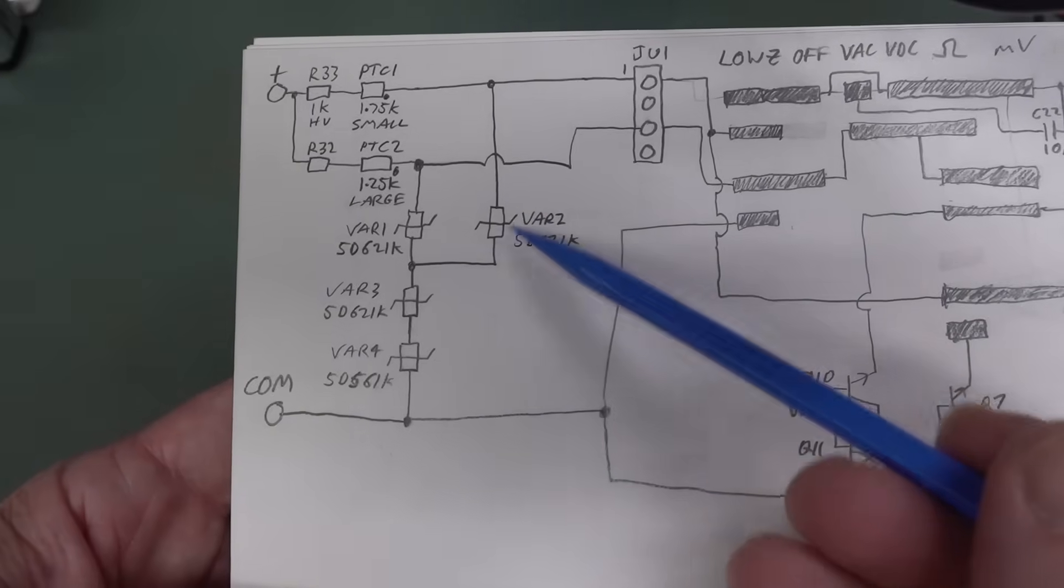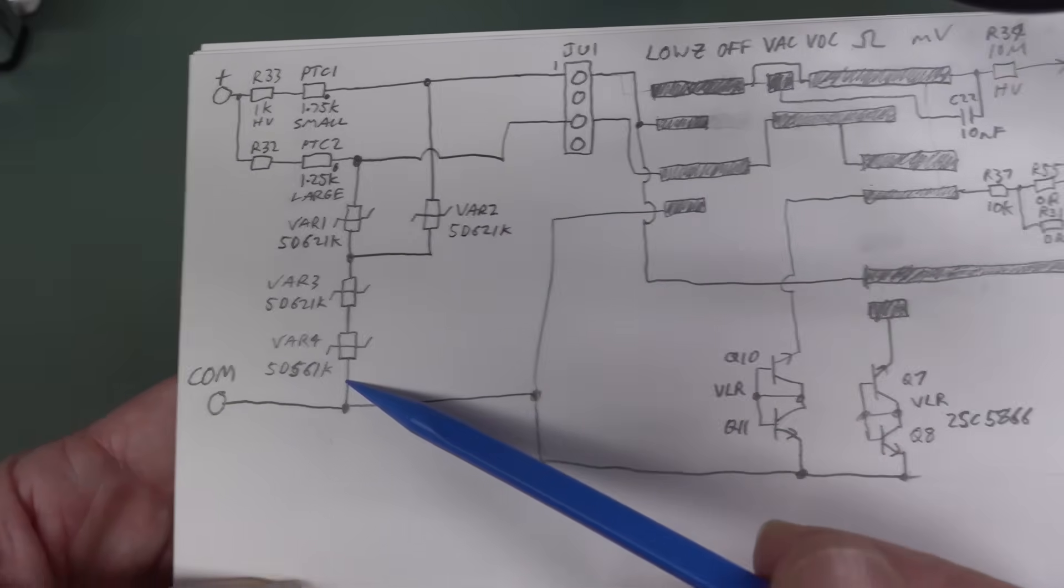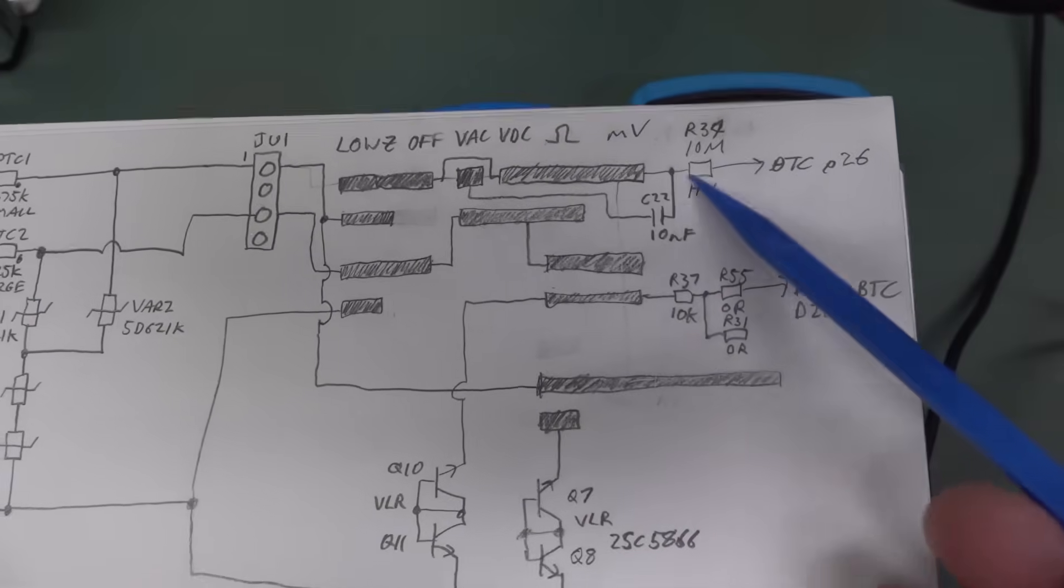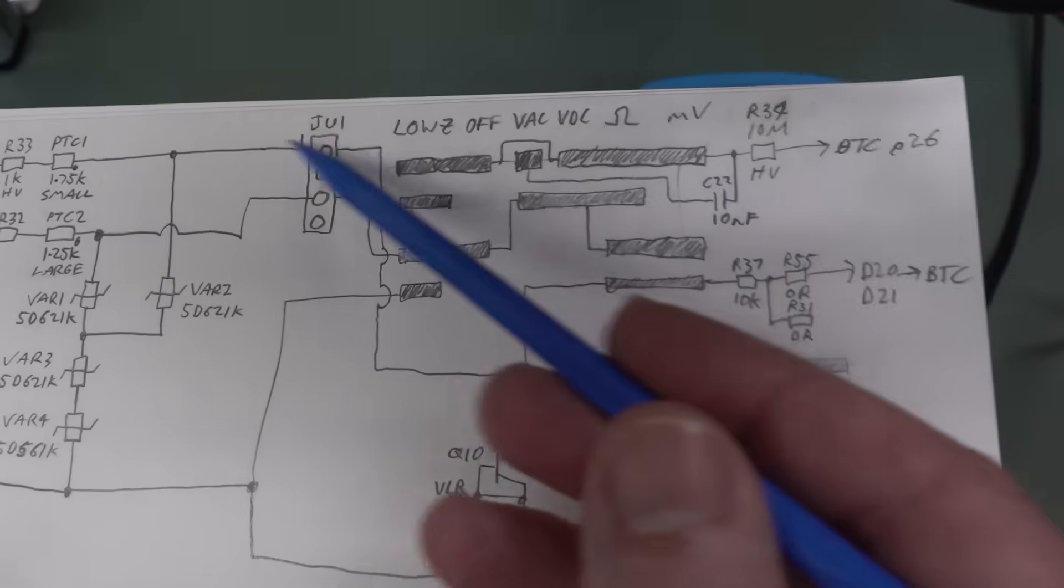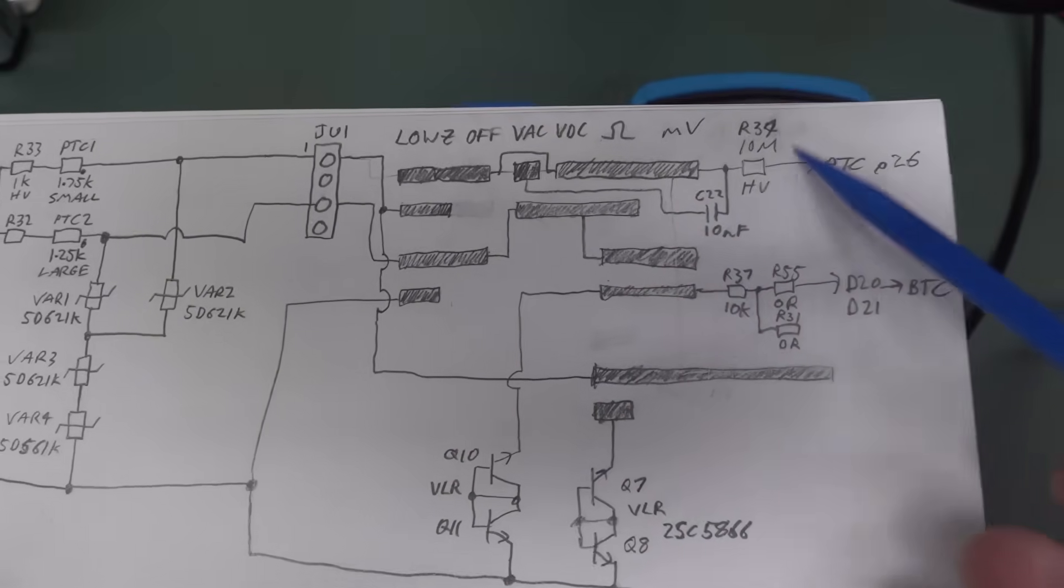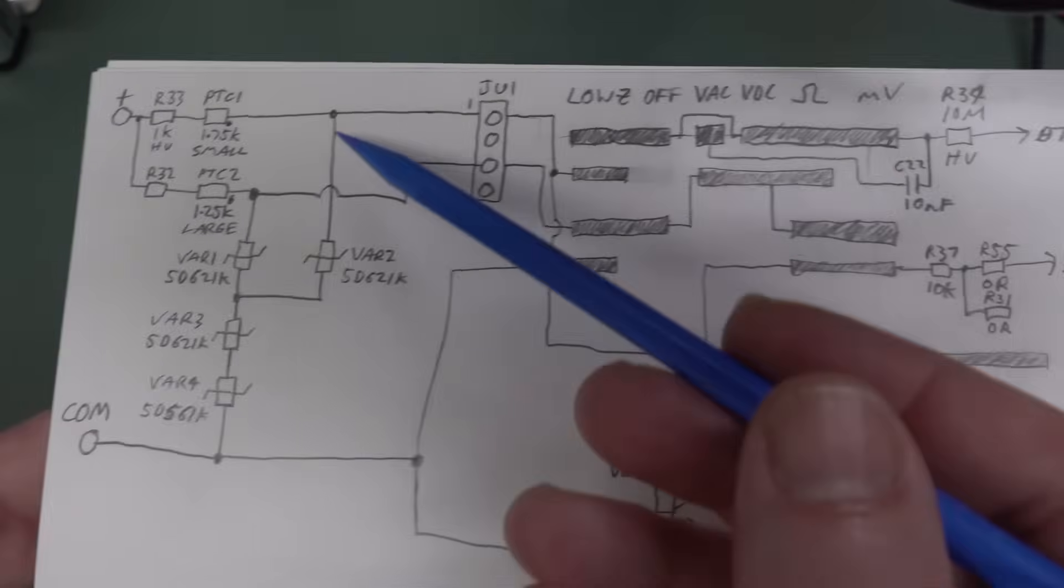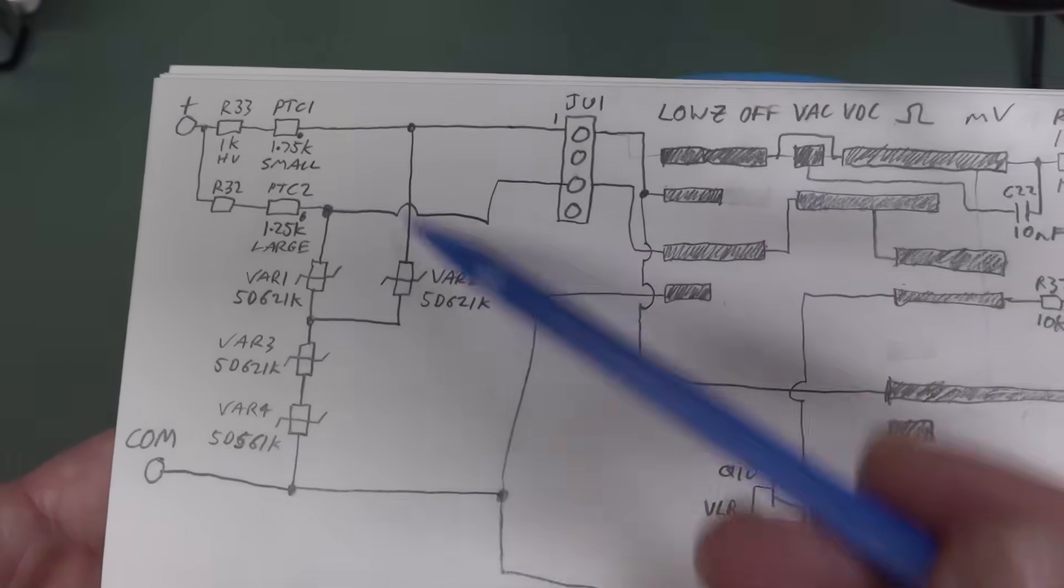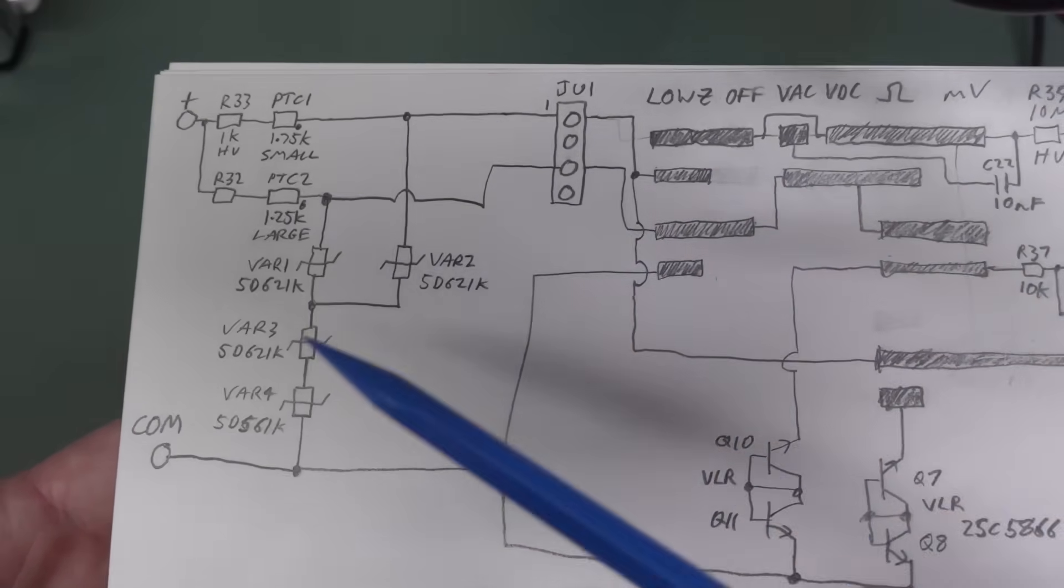But these MOVs are going to have a leakage current through them. So we've got our nominal 10 megaohm input impedance there. So what happens to our nominal 10 megaohm input impedance at say, 1,000 volts? Well, it's interesting. So let's measure it.